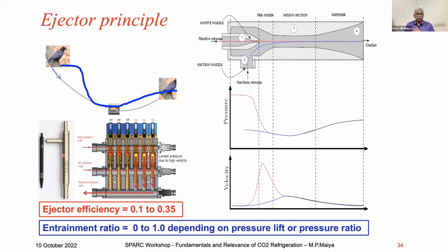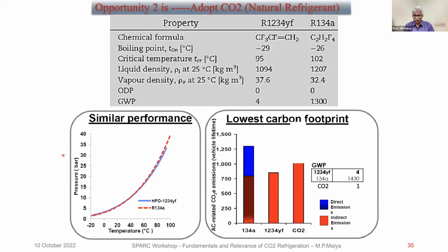Entrainment ratio 0 to 1 depending upon the pressure lift and pressure ratio. You can compare the R134A, the R1234yf, that is HFO, and carbon dioxide. Carbon dioxide looks not competing with these, but with the ejectors you can see it will be better than 134A also.